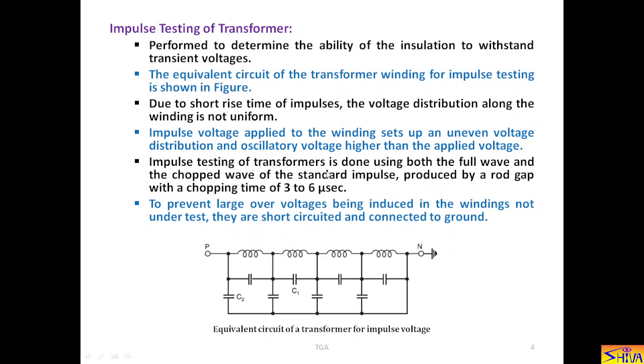Impulse testing of the transformer is done using both the full wave and the chopped wave of the standard impulse. Standard impulse means if it is lightning impulse, it is 1.2 by 50 microsecond. If it is switching impulse, then it is 250 by 2500 microsecond. And chopped wave of the standard impulse is produced by a rod gap with a chopping time of 3 to 6 microseconds.